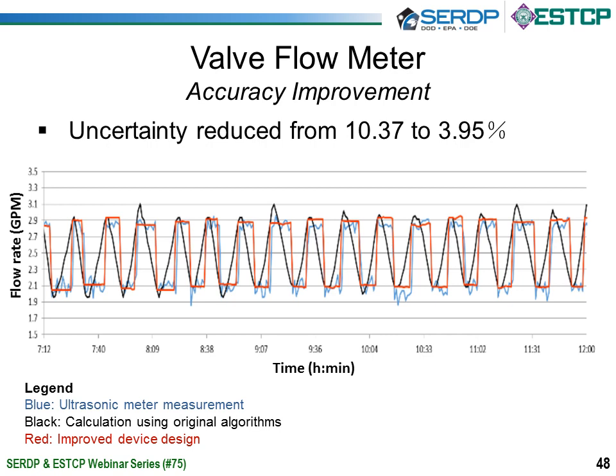And you can see that the agreement is within plus or minus about 0.1 gallon per minute. The rapid variations are not important for us to capture, but you can see that generally the virtual values are within 0.1 gallon per minute of the ultrasonic flow meter measurements. The black line was an early model used for the valve, and you can see that was not nearly as good, and therefore we had to make an improvement in that model.